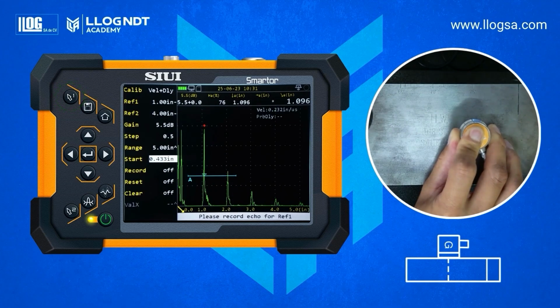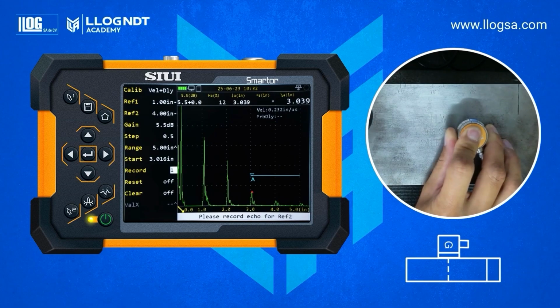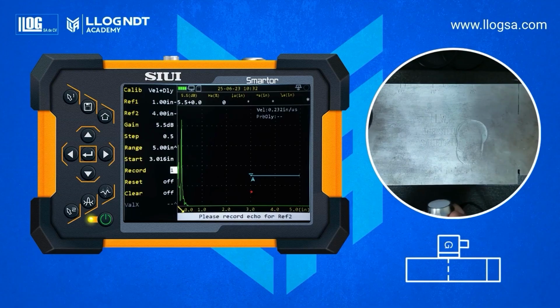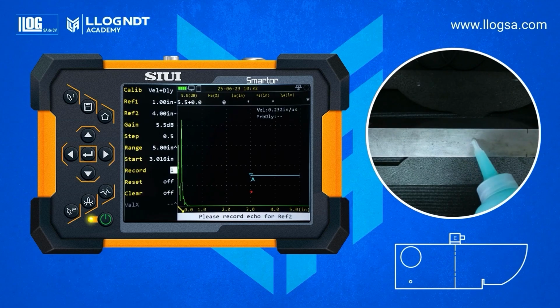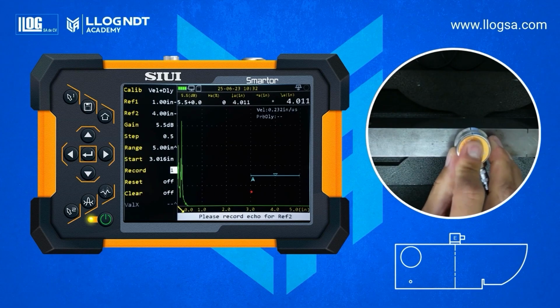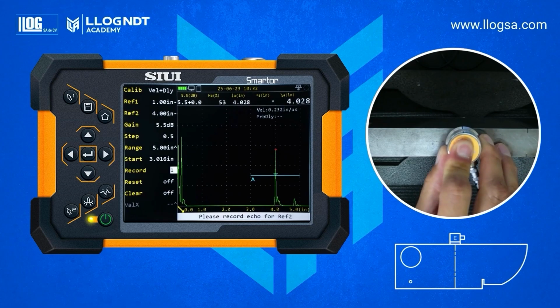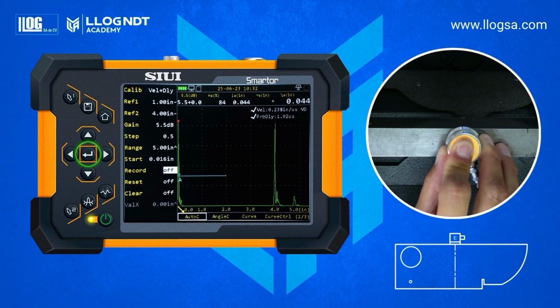Then navigate to the Record function. And press the Enter key to record the first reference. The gate will automatically shift to the position of the second reference. Now place the transducer in position E on the block. And press Enter again to record the second reference. Once the distance calibration is complete, the instrument will display 2 values in the upper right corner: the probe delay and the calculated material velocity.